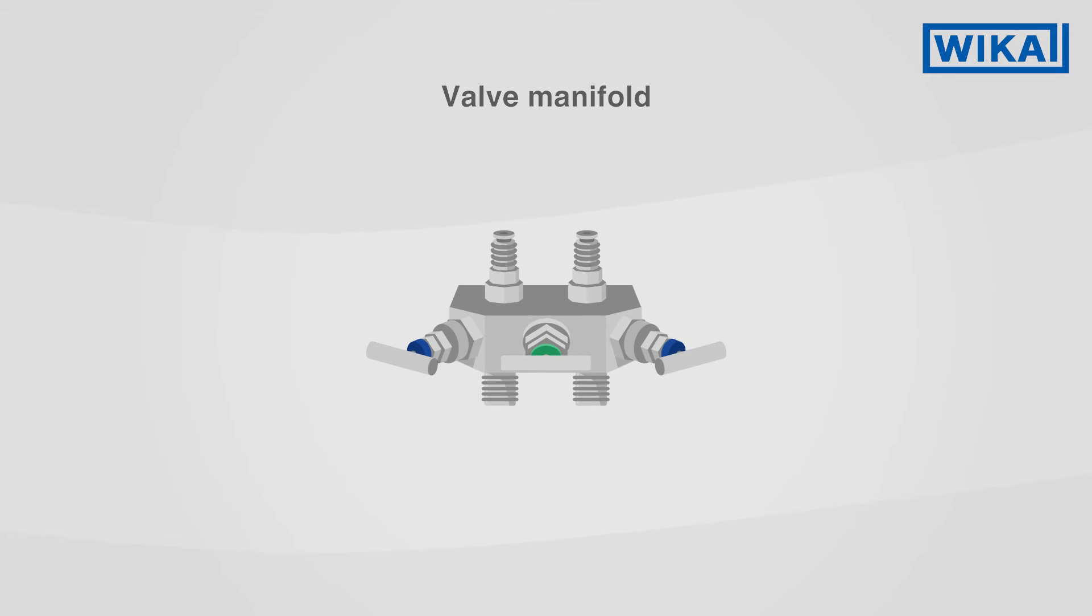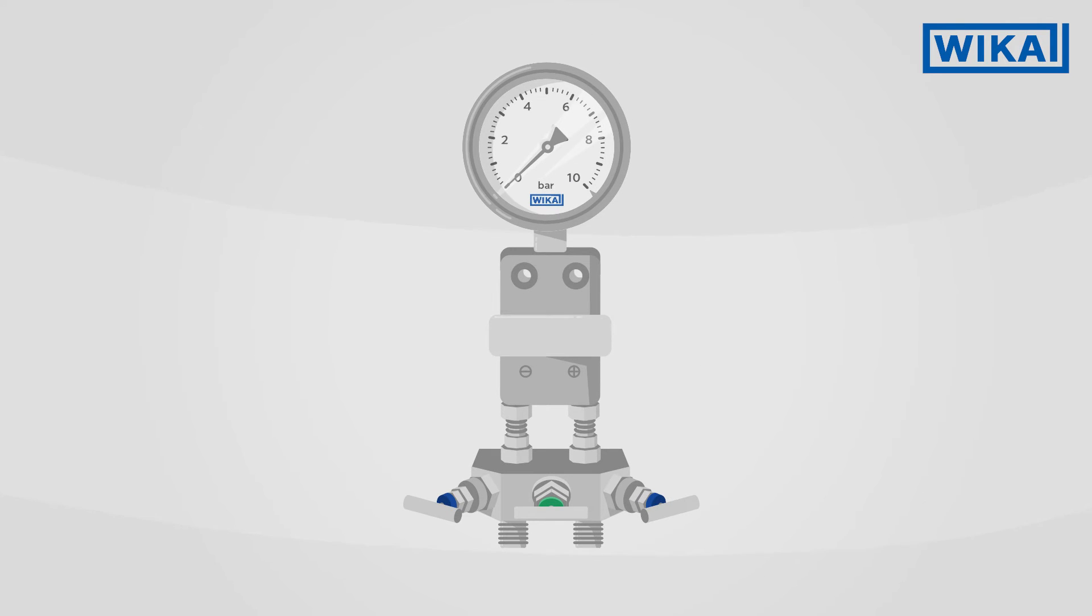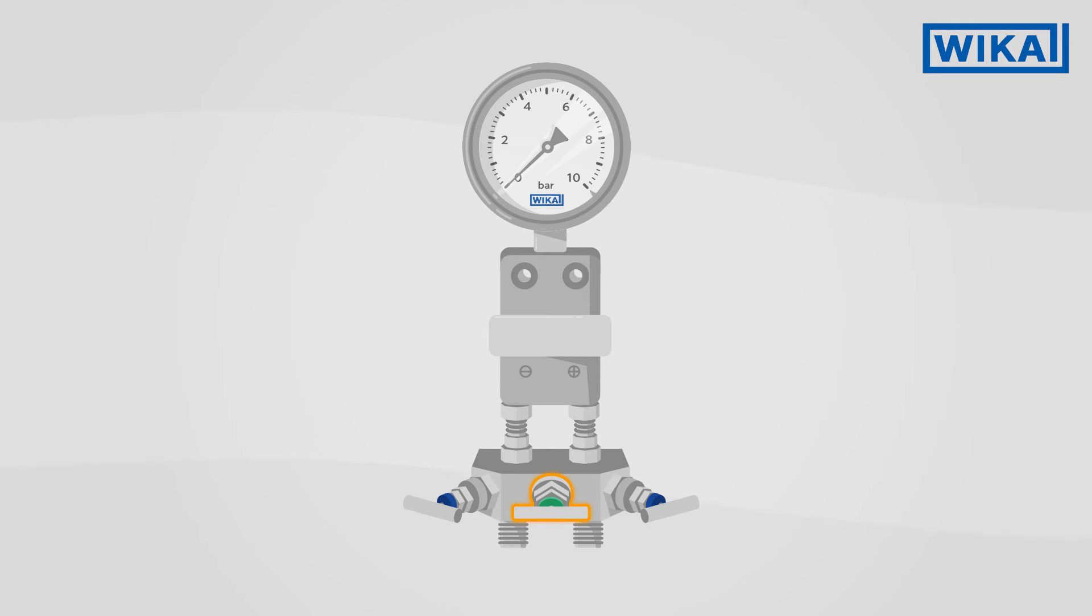Valve manifolds are a special form of needle valve for differential pressure measuring instruments. The shut-off valves separate the process from these measuring instruments. The additional pressure compensating valve enables equalization between the plus and minus sides.